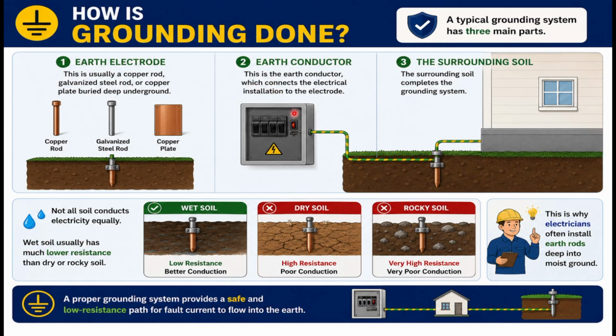You take the earth conductor into the building to your DB, SMDB or MDB, and from there you can connect all your power outlets to it. So basically that's how it is. Bury your earth rod, connect a cable from there to your MDB, and from there you supply everything in the house. We also need to understand that there are different categories of soil, right? We have wet soil, dry soil, and rocky soil. Wet soil normally has low resistance, and it is the best soil for earthing. And we have dry soil, which has high resistance, which is poor for conduction.